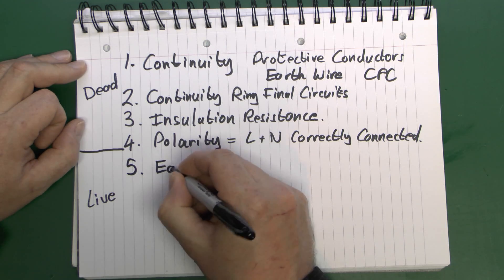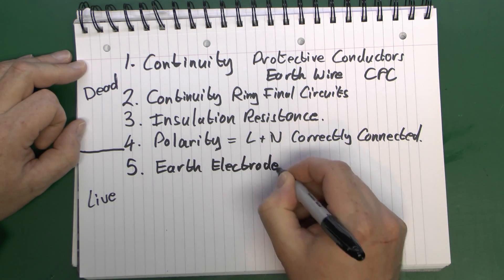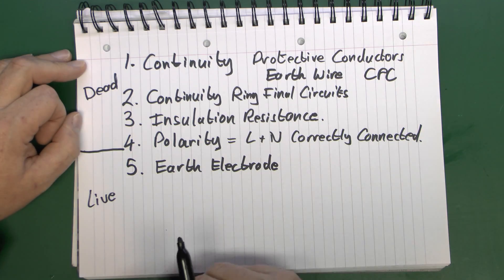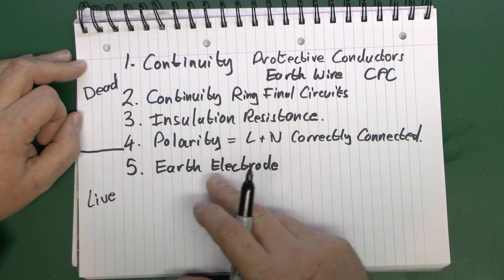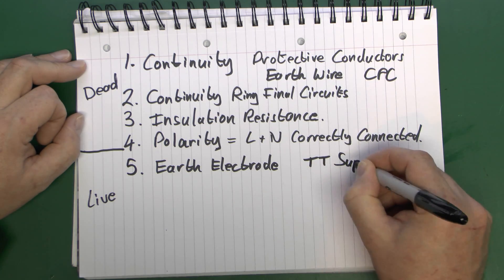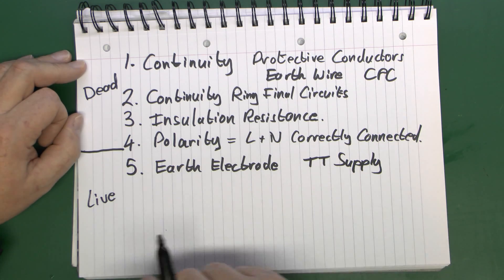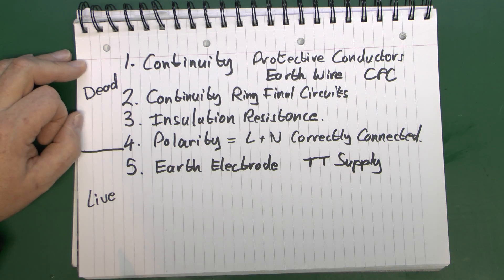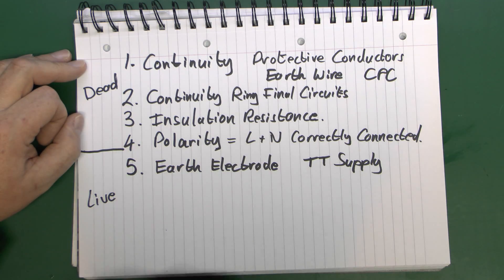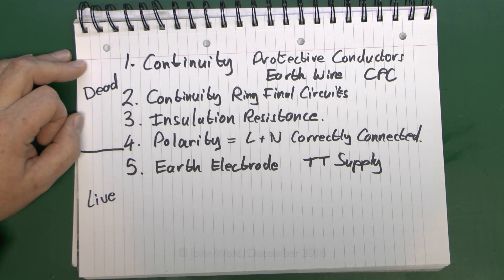Test five is earth electrode. This only applies if you actually have one — the majority of new installations in the UK do not. It's only going to be applicable if you have a TT type of supply, essentially where you don't get an earth from the electricity supplier and you have to provide your own electrode in the ground. That does need to be tested to make sure it's of suitable quality and has been installed correctly. There are a few ways it can be tested, one of which does involve using the power that's already been connected.